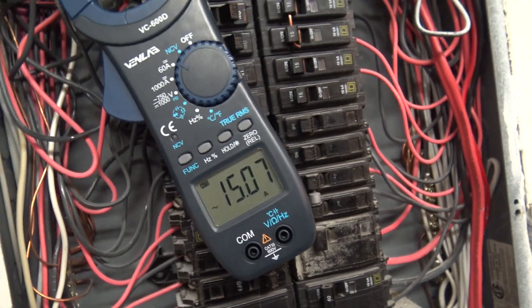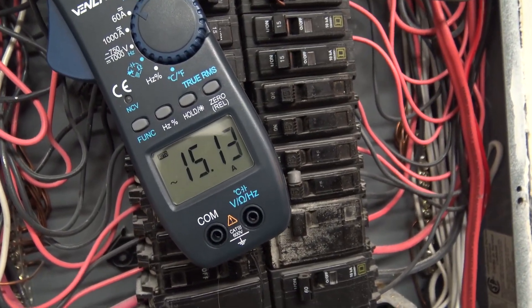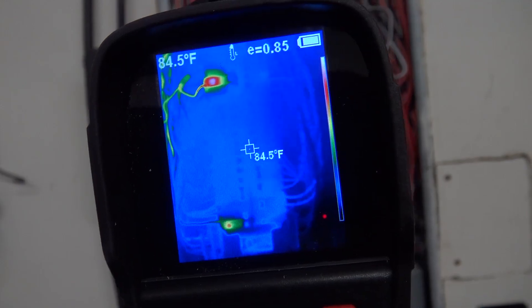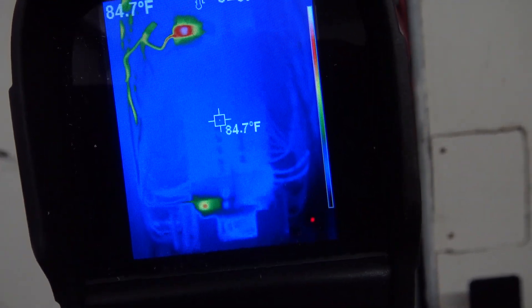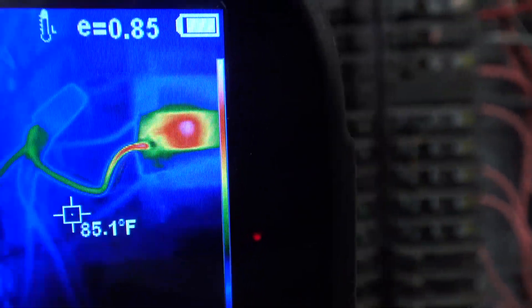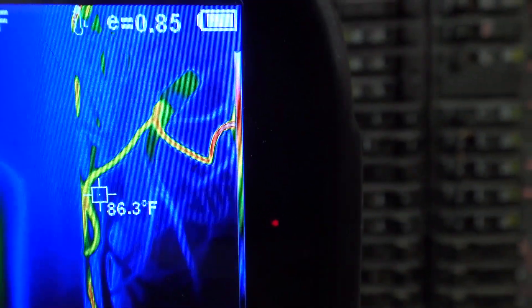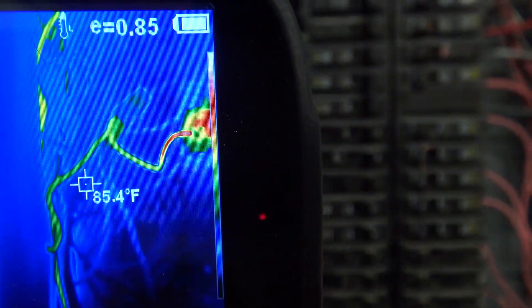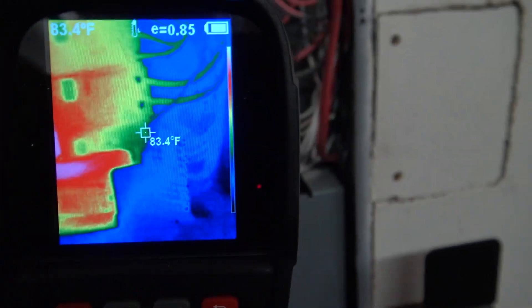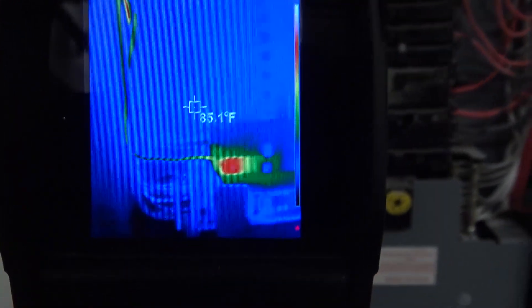Having the breaker trip every 15 minutes is annoying, so it's time for a 20 amp breaker. Looking at the thermal imaging camera, the only breakers that are warm are the ones with current being drawn through them — one is the blower motor for the HVAC, and the other is the AC breaker. You can see the wire going to the air conditioner is warmer than the environment. Looking at the neutrals, they're warm too, but everything else is stone cold.